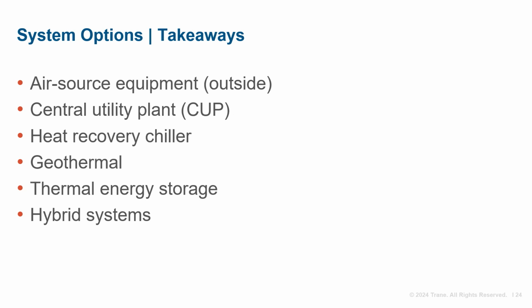The use of energy storage tanks in tandem with geothermal fields can reduce the wells required, and many of the other systems can benefit from the addition of an energy storage property to reduce equipment capacity. The inclusion of thermal storage in the system provides added flexibility, allowing for participation in demand response programs. The key takeaway is that there is no one-size-fits-all solution when it comes to retrofitting electrified heating systems. With that, I'll turn it over to Ronnie for more detail around distribution options.